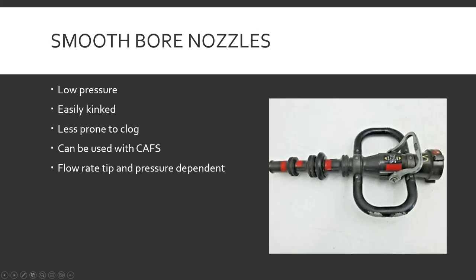Smoothbore nozzles can be used with CAFs — compressed air foam systems. If you were just to hook up an old-school foam eductor to this and try to run foam out of here, it's not going to get air mixed in and it won't foam up. But with CAFs, where they put air into the hose line along with foam and water, it'll come out pre-aerated, so you can get decent foam out of a smoothbore — which is why CAFs is important for smoothbore nozzles.